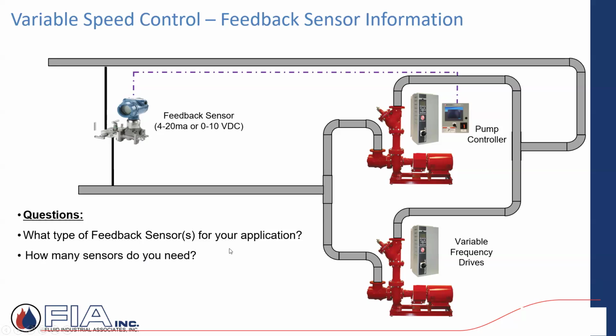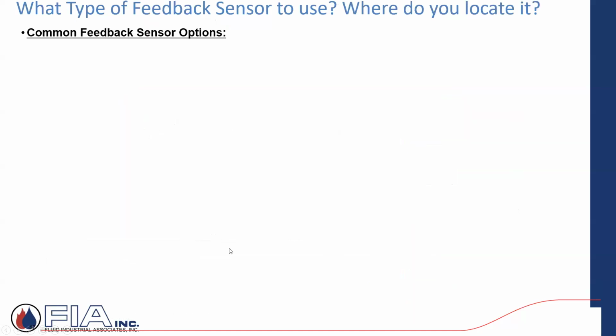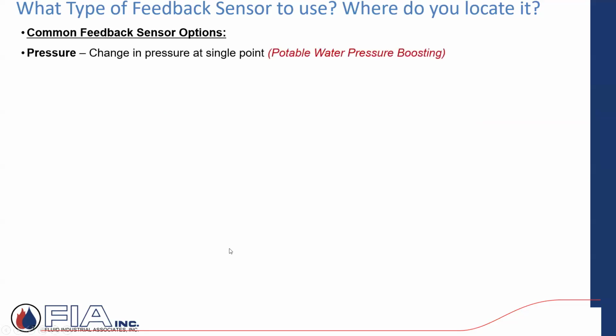So what type of feedback sensors? How many sensors do you need? Where do you locate them? How do you establish that set point for each? What type of sensors? Pressure changes. Change the pressure at a single point. If you're doing a heating system, control loop, closed loop, coils, control valves, that's not the application with just a discharge pressure. But if you're doing a pressure booster package, so a plumbing application, and you get city pressure coming in and you need to boost the incoming pressure for the high-rise building, so you have a discharge pressure, you could use just a simple single point discharge pressure sensor and say, hey, maintain X. As the incoming pressure changes, I'm speeding up or dropping down perhaps my variable speed pressure booster package.